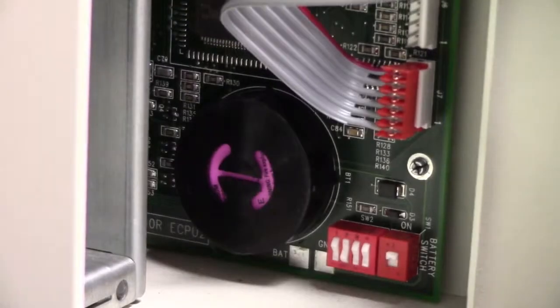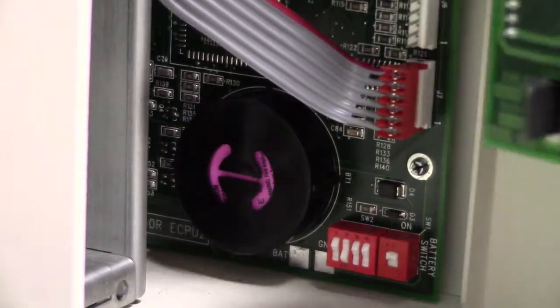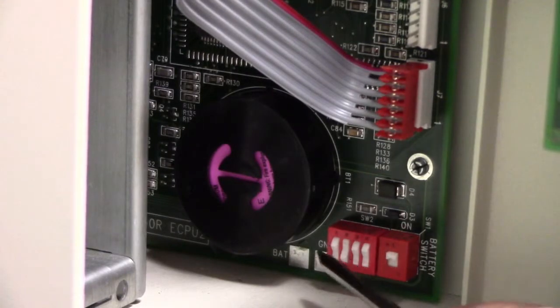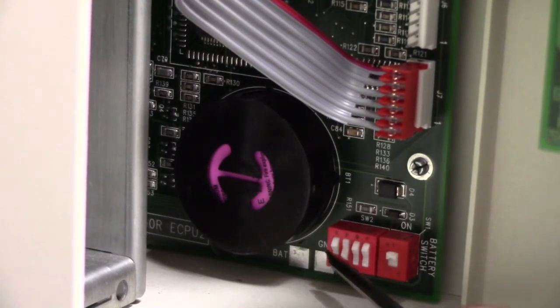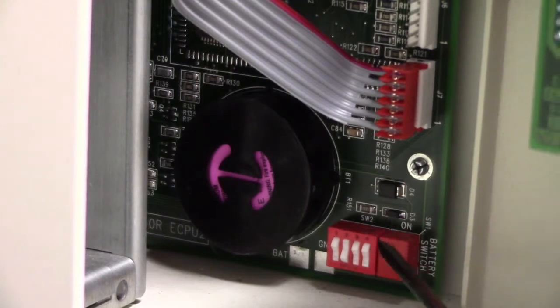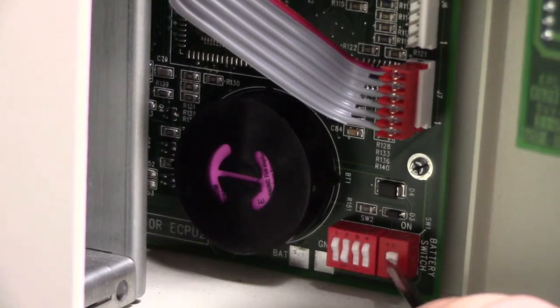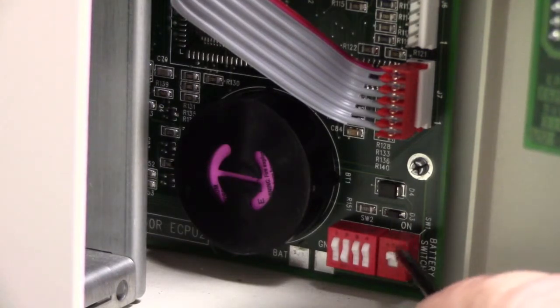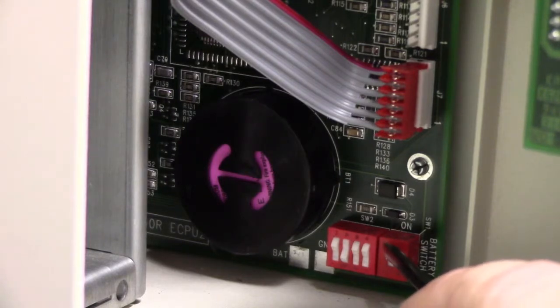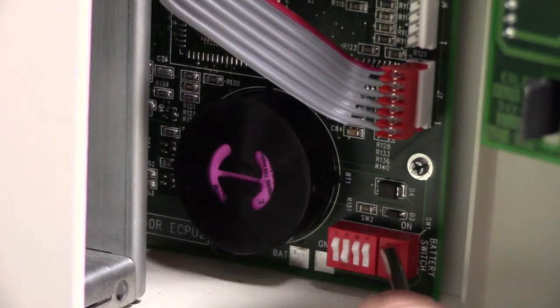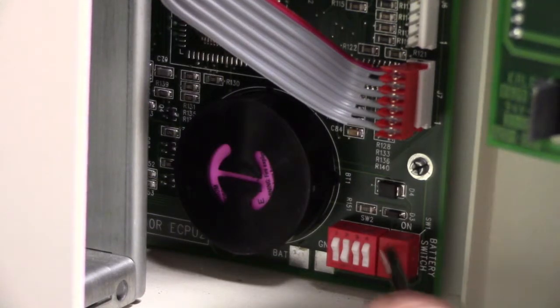Once you have access to the tank monitor behind the printer door, you're going to see two blocks of dip switches. The first is a bank of four. The second is a single switch on its own block. This right-hand switch is the battery switch. From here, with power still on to the tank monitor, we're going to go ahead and flip that off.